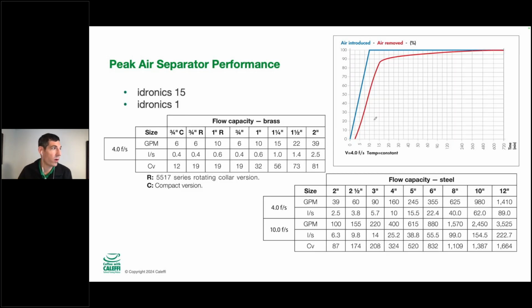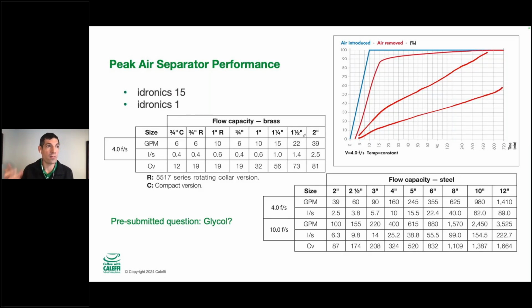It's a multi-pass device. So the way that we size that is 4 feet per second is a good maximum to use for the brass devices. It's also a good number to use for the steel devices. We will publish a higher flow rate, but it's just going to take longer to separate that air out. Over the course of the day, it's probably going to get to the same 99.9% air removed number, but that's one thing to keep an eye on. Also, if you're trying to move 100 GPM through 2-inch pipe, you're probably breaking some other velocity rules somewhere else in the system. So they don't stop working at 4 feet per second. You're just going to stretch out that performance a little bit. With glycol, you're going to stretch it out even further because it's harder to get that air out of the kind of oil viscosity that glycol can have sometimes. So it'll take a longer amount of time to get that performance.